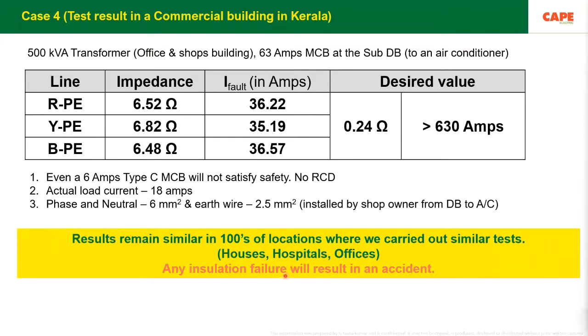Now, from my experience in the last 1.5 years, I have tested, or not me directly, some of my engineers, or we have an association with a lot of electrical contractors who regularly attend our trainings. We ask them to buy the meters and they go to their client's place and do the testing. Out of this, results similar to this shop are remaining in hundreds of locations across India. I would say more than 90 to 92% of our installations have similar earth fault protective measures. Means there is no safety at all. It is common in houses, hospitals, and offices. Any insulation failure will result in an accident.